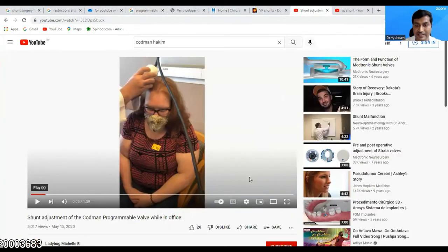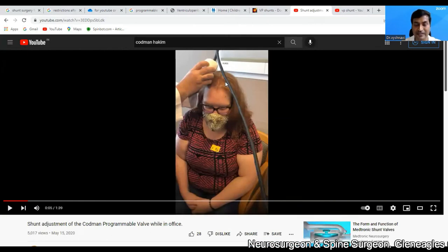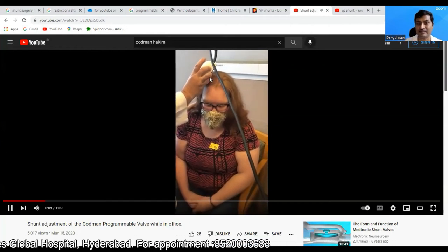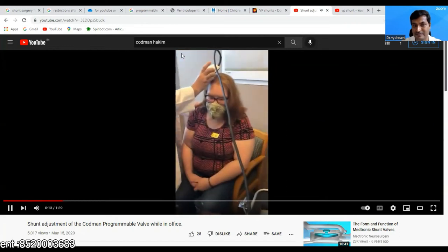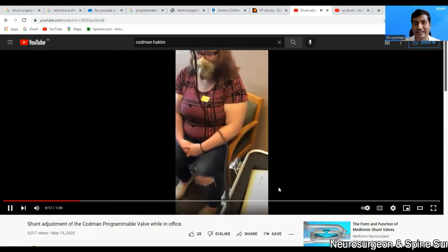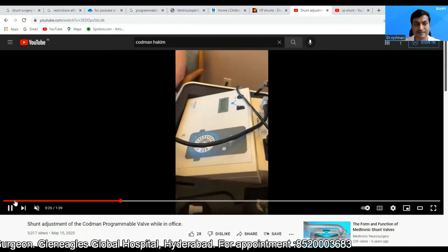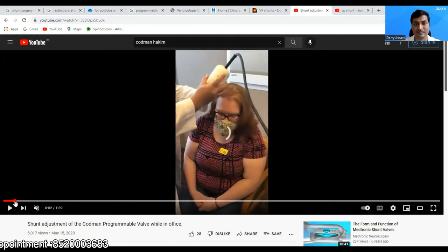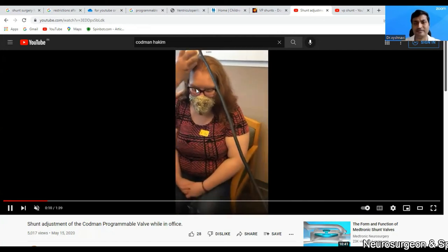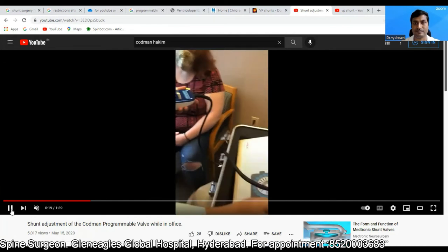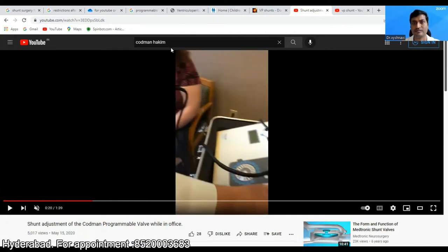Here is a video showing pressure adjustment. What the doctor is holding is a device placed over the valve — this external machine performs the pressure adjustment. It is just like Bluetooth — I place this device over the valve, switch on the machine in my OPD, and the shunt is adjusted. That's all. This ensures prevention of over-drainage and under-drainage in at least 95% of patients.